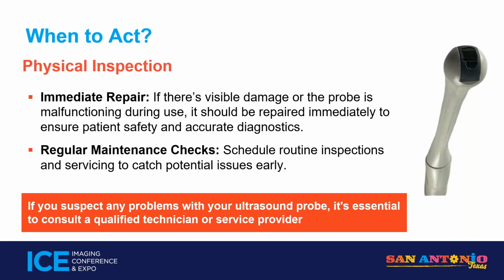Regular maintenance checks. Again, I recommend 2 PMs a year on ultrasound. And GE learned it for everybody. They just put in their service manual that no PMs are required. But you need to read the whole paragraph because it says no PMs are required because there's no moving parts that cause excessive wear. However, it keeps on going and says that there are other things that need to be checked. And you should do, for example, your filters weekly. Well, if you don't do any PMs, I can guarantee the sonographer is not going to check their filters weekly.